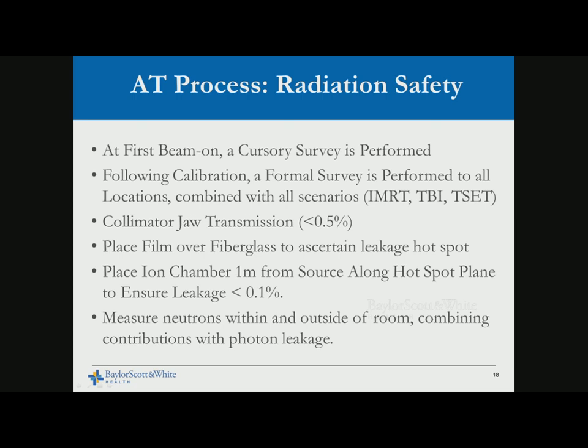The radiation test begins with a cursory survey at first beam-on to ensure all shielding goals are met. Following that, you do a formal full survey to confirm primary and secondary barriers are properly constructed. Leakage from the LINAC must be 0.1% of the isocentric dose. For LINACs with energies greater than 10 MV, you need to measure the neutron contribution from photoneutron interactions.